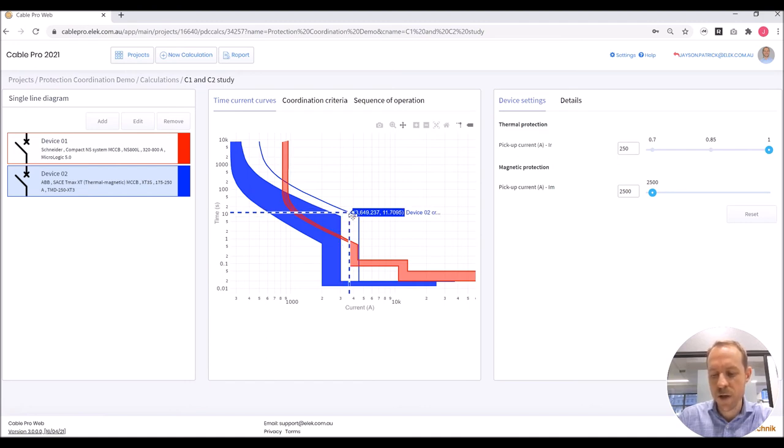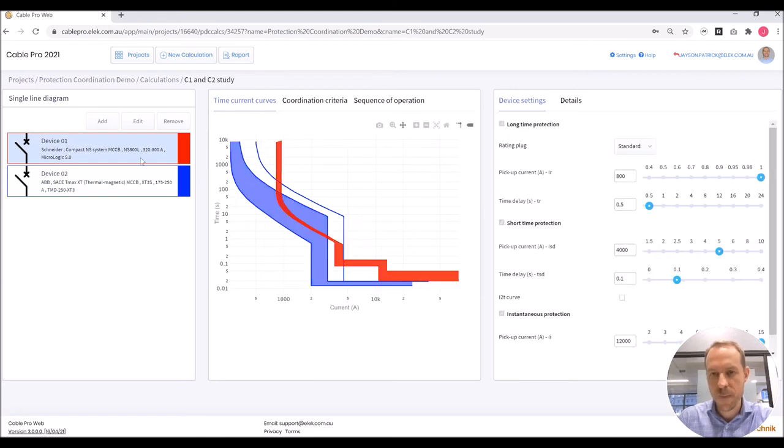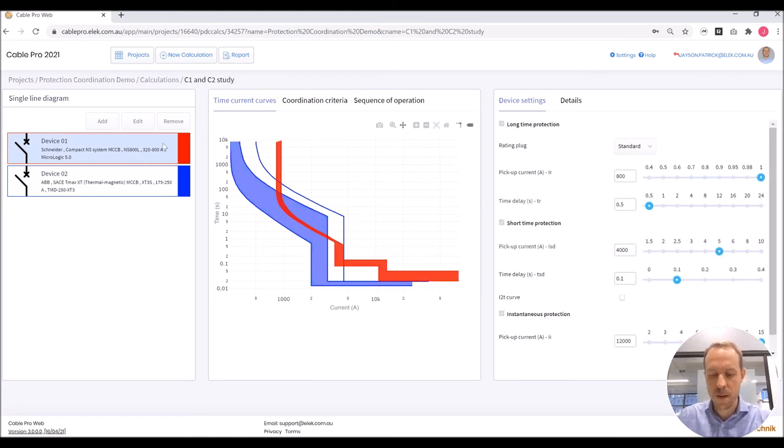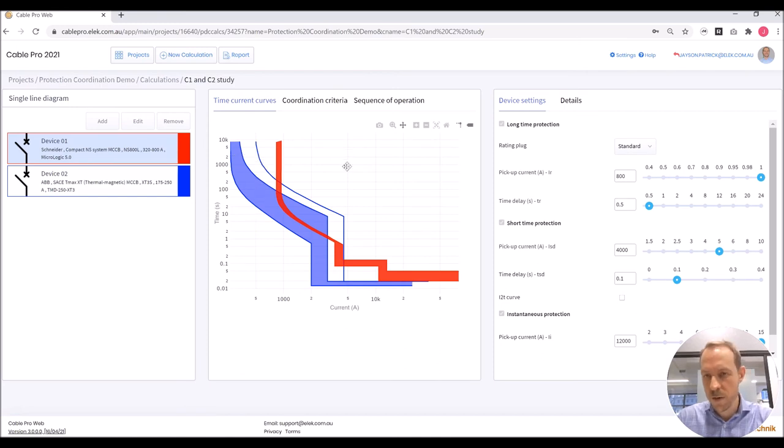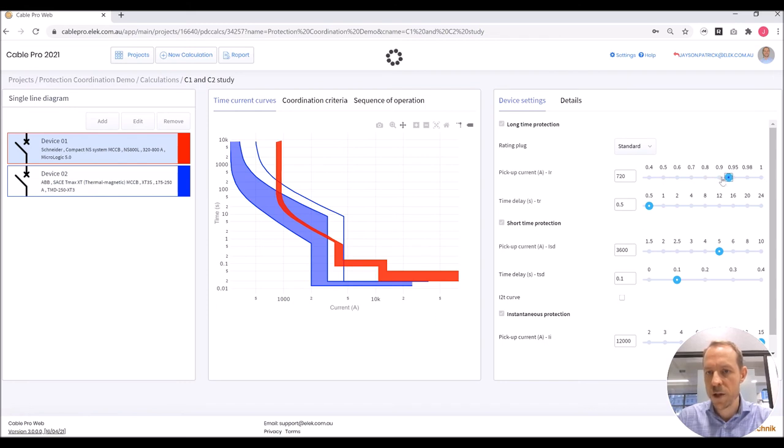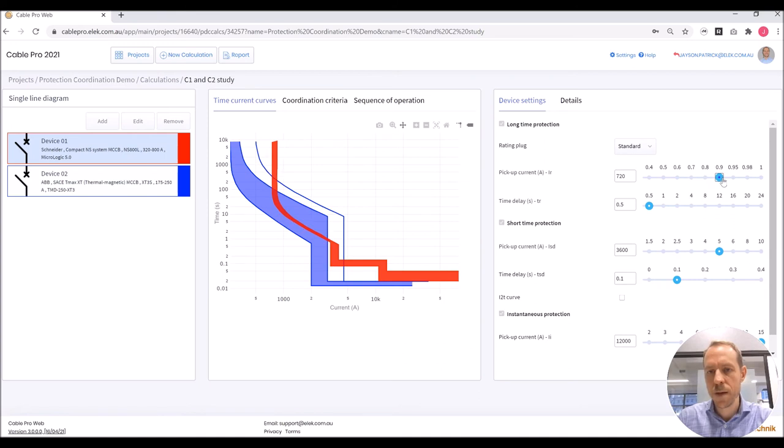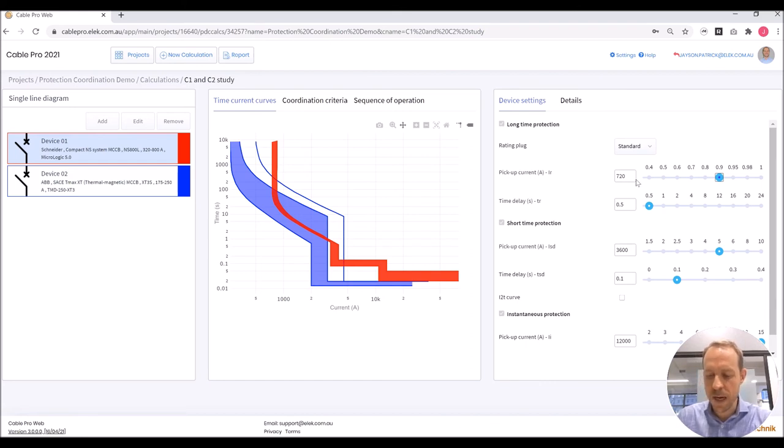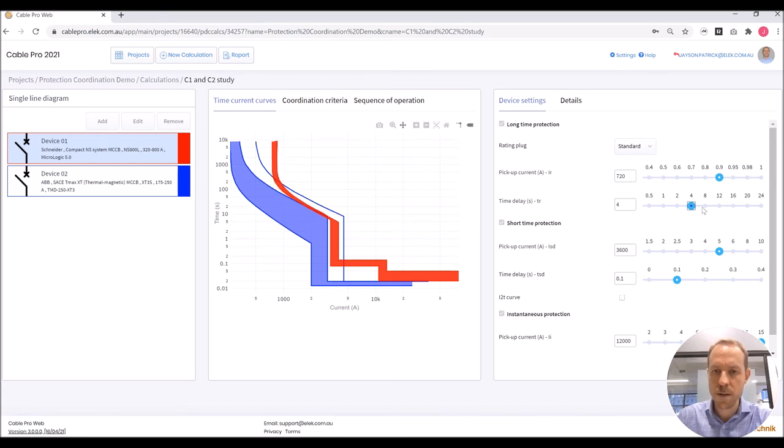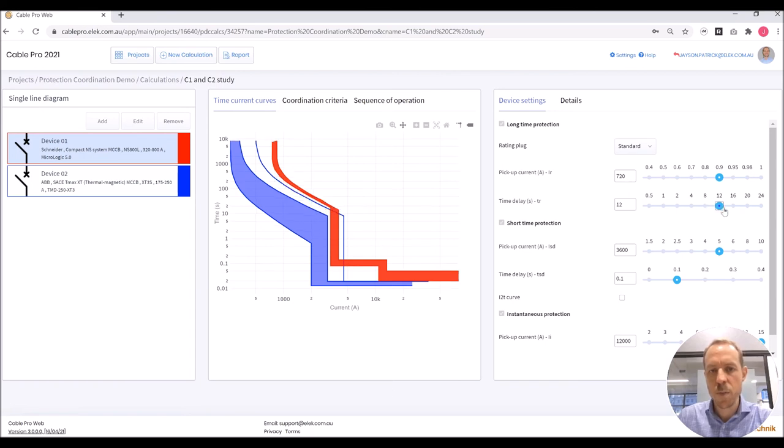So I'm going to adjust the settings. I'm going to start with long time protection and adjust that to just above what we needed. That setting is 720 amps. Next I'm going to adjust the time delay and see if that helps us. You can see the red curve moving to where we need it to.